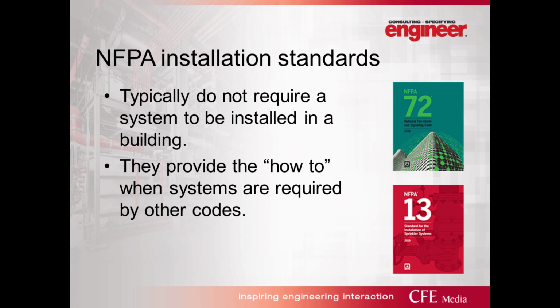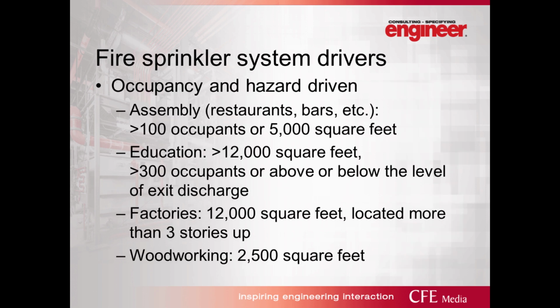Now, once a requirement has been established, then we go to installation standards for how those systems should be installed. So the two that are very prominent: NFPA 72 is the fire alarm code, and NFPA 13 is the sprinkler standard. These documents provide the how-to when it comes to system design and installation. Right? These documents do not require systems. So sometimes I'll hear someone say, well, does NFPA 72 require smoke detectors, or does NFPA 13 require sprinklers? These documents are actually telling you how to design them and how to install them when a building or fire code otherwise requires them. Okay.